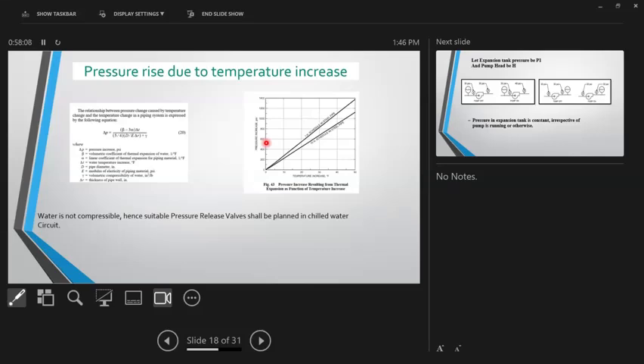Your valves, your heat exchangers, those are not designed for that 41 bar kind of pressure. Why does that happen? Because water is not compressible. You can see for a simple 1 inch pipe with hardly a 20 degree Fahrenheit rise, your pressure increase is becoming unmanageable. That's why the expansion tank in the system is very, very necessary.